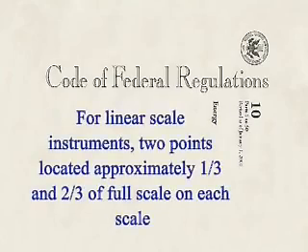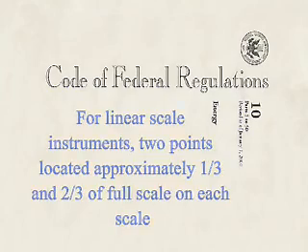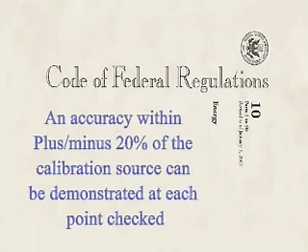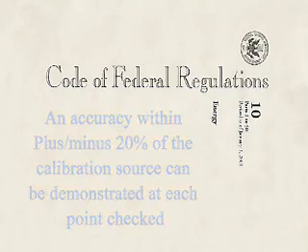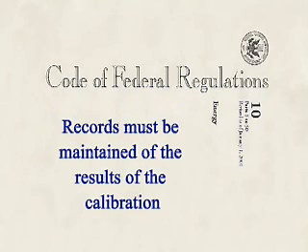For linear scale instrument calibration, at least two points located approximately one-third and two-thirds of full scale on each scale must be checked. Survey meters must be calibrated so that an accuracy within plus or minus 20% of the calibration source dose rate can be demonstrated at each point checked. Records must be maintained of the results of the calibration.